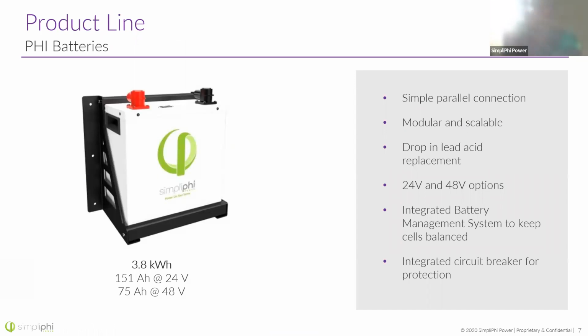We're going to talk a little about the Phi batteries as well. This Phi battery has been a real workhorse, installed all around the world. We have two different options: 24 volt or 48 volt. We never run these in series, so you cannot take two Phi batteries and put them in series to get 48 volts. You cannot start with 24 and get 48 volts, so please never do that. If you need a 48 volt solution, start with a 48 volt battery. We only ever run our batteries in parallel, so the battery management system can adequately address balance of system needs.